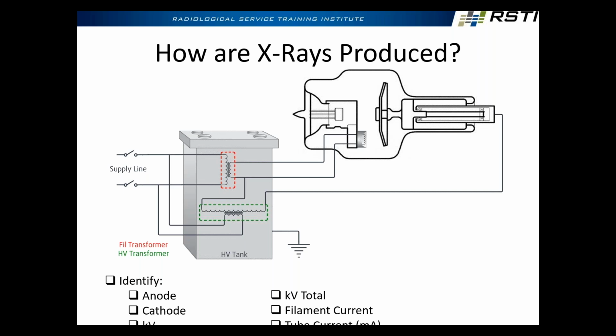So in this case, we don't see any rectification or anything like that. But if I were to have my single phase AC coming in here, stepped down here, stepped up there, when it gets to the tube, the thing that we have to remember here is that the cathode is always negative, the anode is always positive, and electron flow is always from negative to positive, right? So we can only conduct from cathode to anode. We can't conduct the other way around. So if I were stepping up that voltage, anytime I was on the positive going side of that waveform, I would be conducting across the tube.